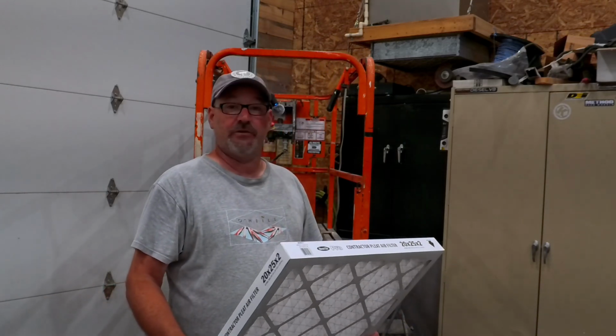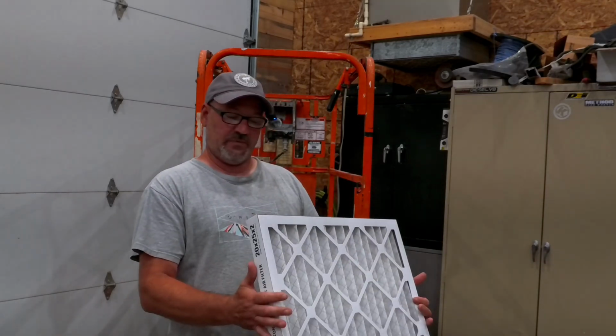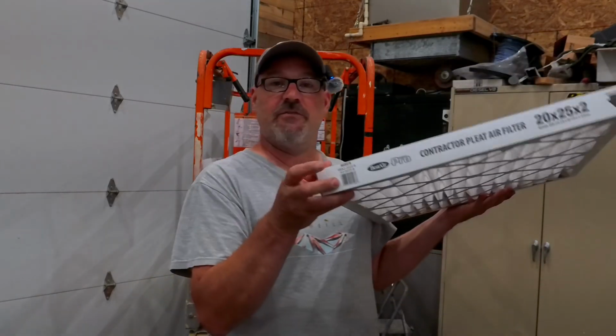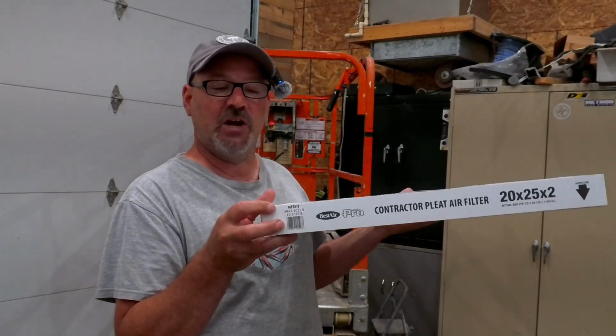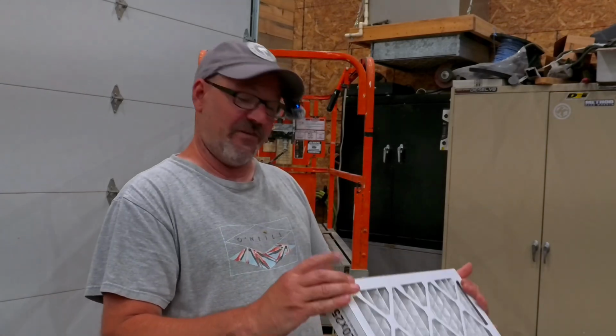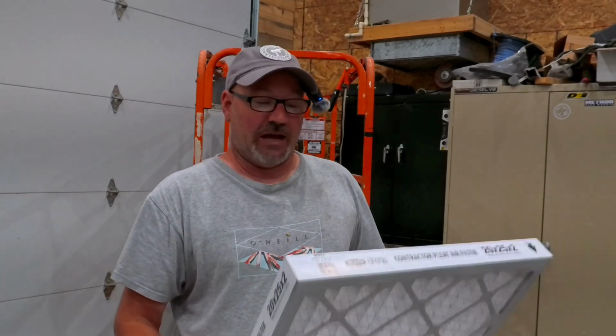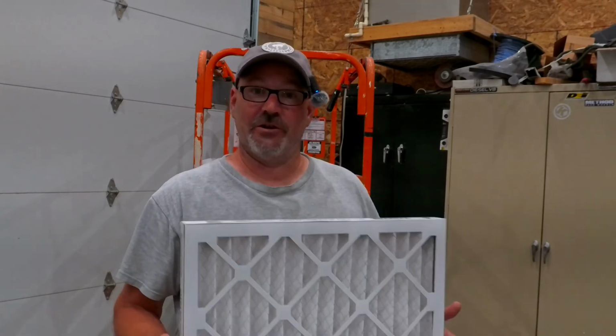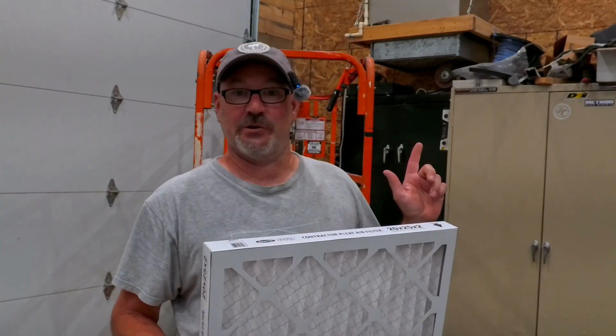Number two, filter quality. Don't buy the cheapest ones on the market. A simple thing to look at here is that all filters have what they call a MERV rating, M-E-R-V. This is a MERV rating of 8. Anything from like an 8 to a 13 is a good filter. Anything over 13 is more for hospital use and stuff like that. Anything under like a 6 or a 7 is not really going to filter the air. The object of a filter is to collect the dirt before it gets trapped in your A coil. Once that's in your A coil, well, then you've got a service call.